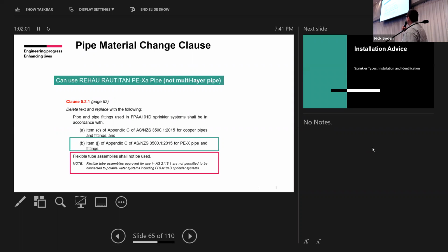A bit of a change is the use of Appendix C of the standard for PEX pipe and fittings. So flexible tube assemblies shall not be used. Normally you see your galvanized system, you've got a T-piece and you've got your flexible hose. Traditionally the galvanized pipe and those flexi hoses aren't watermarked as well. That may change in the future, but at this stage it is only the PE-Xa pipe that is available, and that's why instead of a flex hose section, we'll actually utilize this with a hanging rod sticking up, and then there's an adjustment screw here within the escutcheon plate, which I'll go through as well, for your last adjustments.